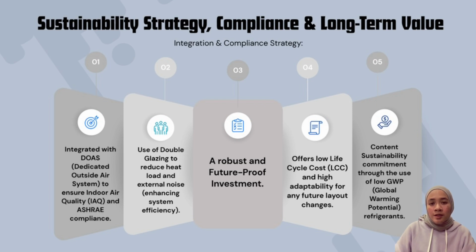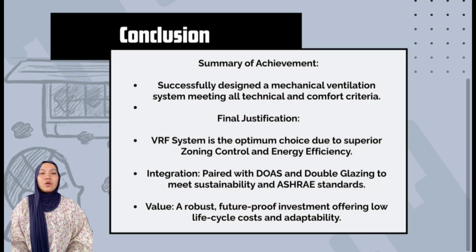Switching to the long-term strategy and sustainability, we ensure that this project is not only efficient but also responsible and future-proof. First, in terms of integration, our VRF system is integrated with a DOAS, or dedicated outdoor air system. This integration is key to ensuring excellent indoor air quality (IAQ) and compliance with ASHRAE standards. Second, our building fabric strategy involves the use of double glazing. This measure reduces heat load and noise from the industrial area, thereby enhancing the overall efficiency of the system. Third, we are committed to sustainability through the use of low GWP (global warming potential) refrigerants. Overall, this system represents a solid, future-ready investment. It offers a low life cycle cost (LCC) and high adaptability should changes to the building layout be required in the future. Here is the conclusion of our project.